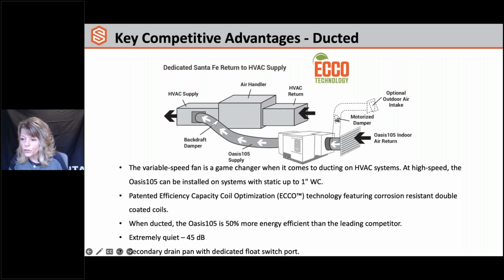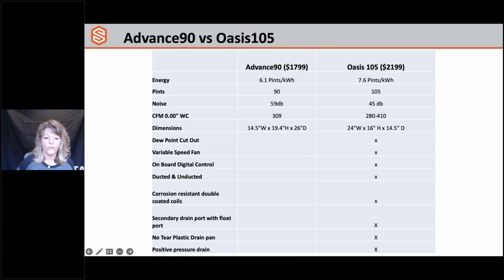Are there published CFM numbers for low and high speed at given statics? So I don't know if Ryan, our product manager, made it on here or not, if we have those published numbers, but you should be able to keep the CFM by adjusting that fan at the different statics. So previously I showed that, let me see here, I think we go up to 400 CFM on our 410. So you can adjust the fan speed based on the different statics in order to maintain your CFM. But I will get with Ryan and make sure that if there are any published numbers that we have beyond this, to get that to you, Mike.